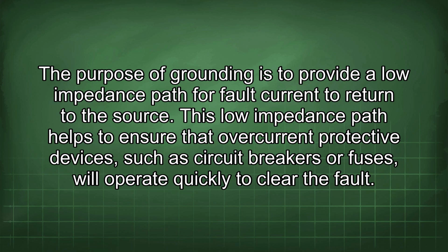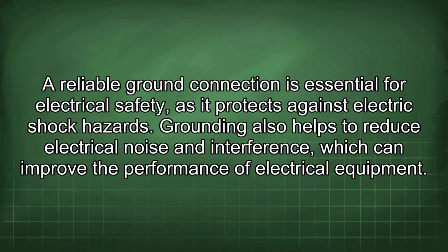This low impedance path helps to ensure that overcurrent protective devices, such as circuit breakers or fuses, will operate quickly to clear the fault. A reliable ground connection is essential for electrical safety, as it protects against electric shock hazards. Grounding also helps to reduce electrical noise and interference, which can improve the performance of electrical equipment.